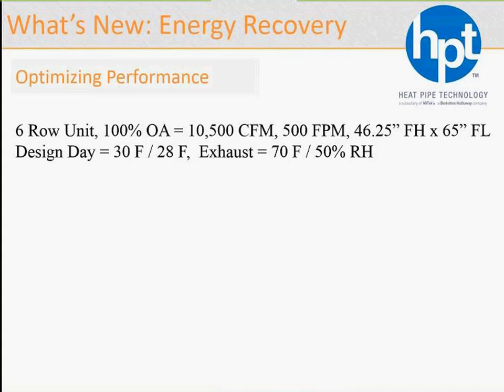Let's look at an example of a 6-row, as we said earlier, which is the sweet spot for energy recovery heat pipes. We're looking at 100% outside air conditions for 10,500 CFM, the usual 500 feet per minute, a design winter day of 30 degrees, and the usual exhaust of 70 degrees, 50% RH.